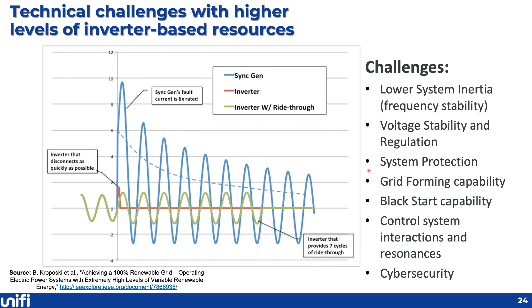Another piece is the black start capability. If the grid goes down, how can we restart it? Right now we typically do that with diesel gen sets that start up power plants that then reconnect the rest of the grid piece by piece. But if we have a 100% inverter-based grid, can we restart the entire system, using a variety of techniques? Then there are control system interactions, potentially new resonances that may occur from all these power electronic devices, and finally cybersecurity concerns. So there are a number of challenges to getting to these really high levels of inverter-based resources, although I would say they're all manageable, and we can come up with solutions, and we need to in the very near future to get to these high levels of renewables.